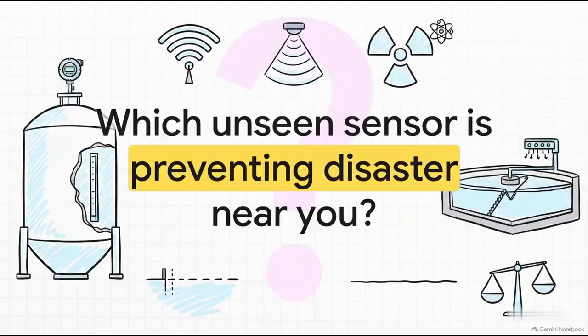And for dry powders that would just jam up a mechanical float, you pivot to capacitance or radar. The level of thought and engineering packed into these relatively small devices is truly staggering. They are total unsung heroes of our industrial age. So the next time you drive past a massive industrial facility or a water treatment plant, don't just look at the giant steel structures. Ask yourself what unseen sensors, whether it's radar, ultrasonic, or even nuclear, are silently and accurately measuring the depths to keep everything perfectly balanced and utterly safe.